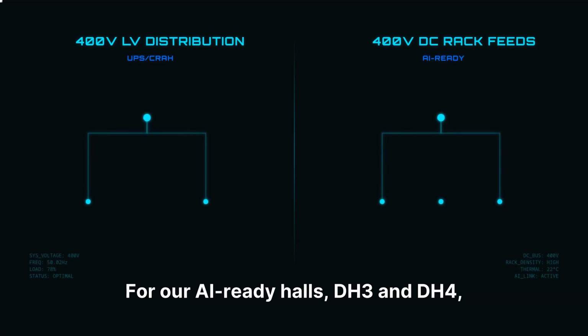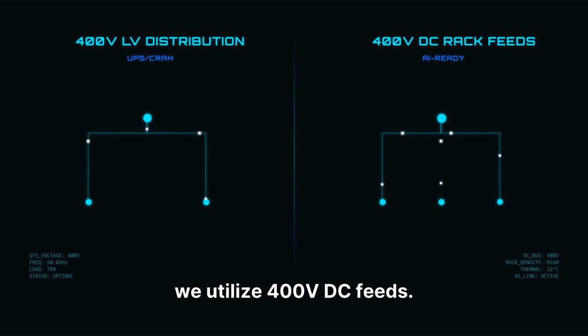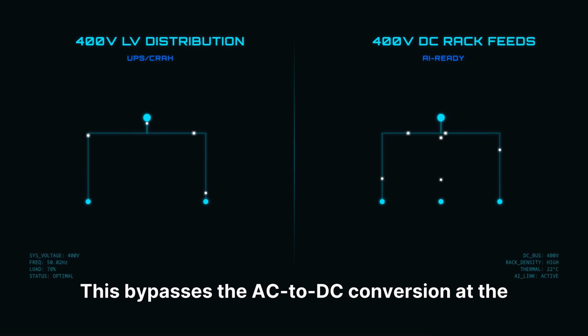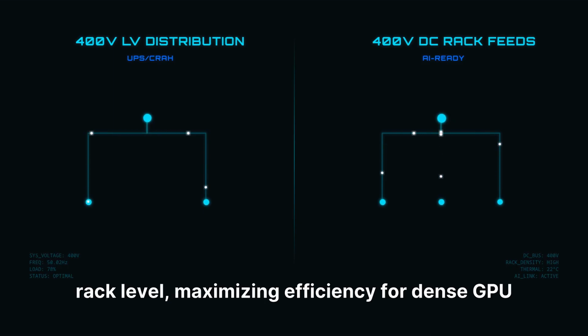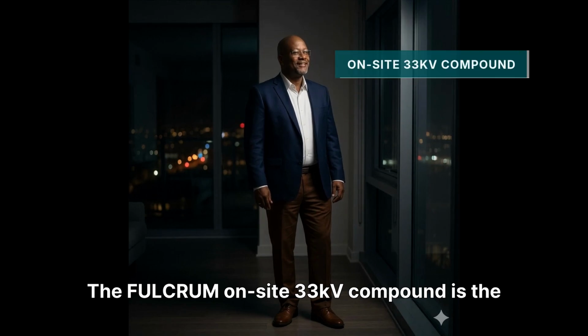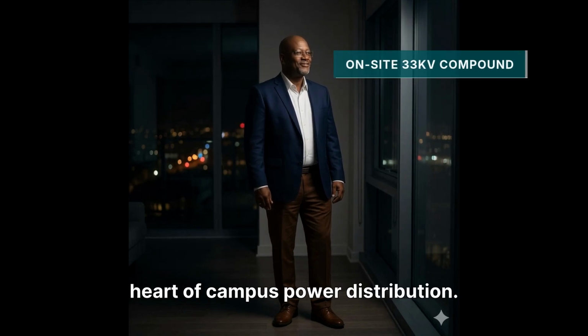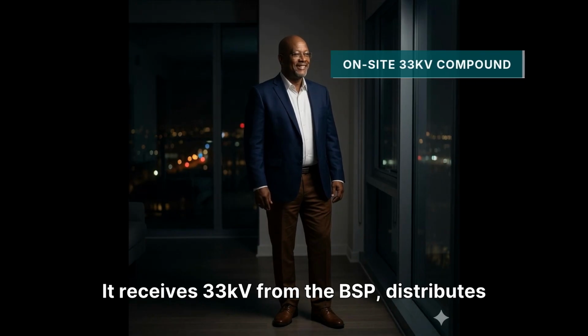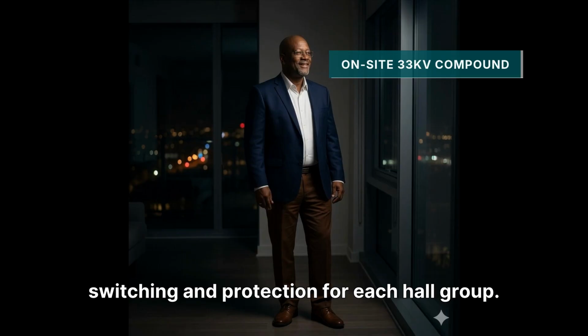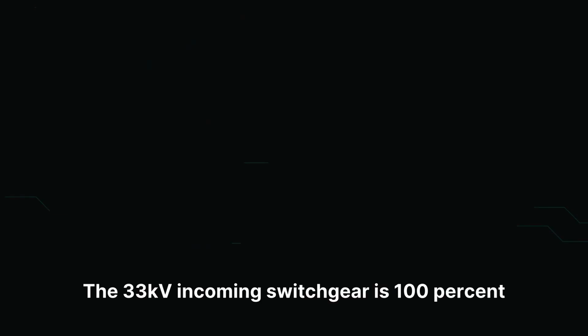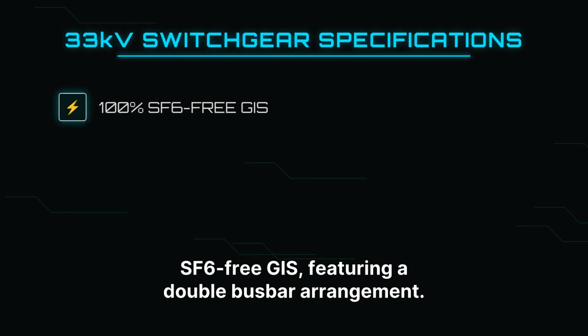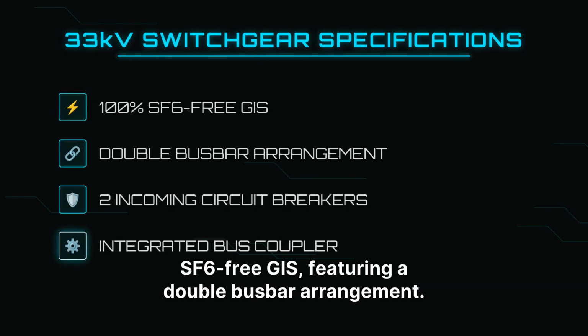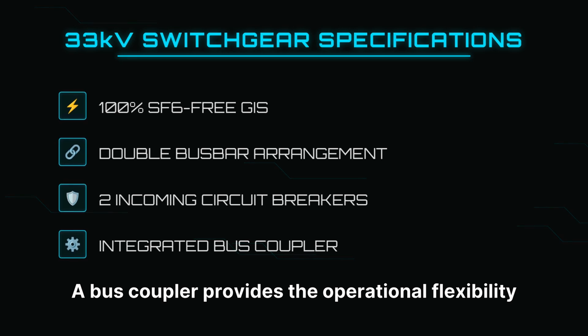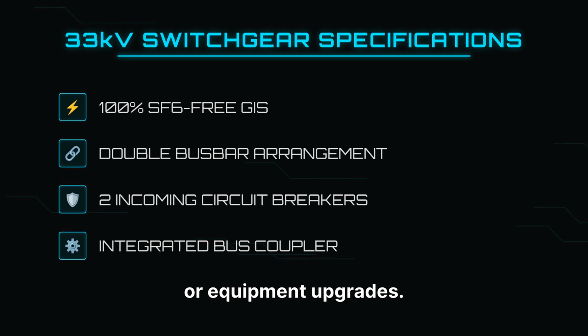Finally, 400 V LV powers the UPS and cooling infrastructure. For our AI-ready halls, DH3 and DH4, we utilize 400 V DC feeds. This bypasses the AC to DC conversion at the rack level, maximizing efficiency for dense GPU workloads. The FULCRUM on-site 33 kV compound is the heart of campus power distribution. It receives 33 kV from the BSP, distributes it around the ring, and provides the switching and protection for each hall group. The 33 kV incoming switchgear is 100% SF6-free GIS, featuring a double busbar arrangement. A bus coupler provides the operational flexibility we need to maintain power during maintenance or equipment upgrades.